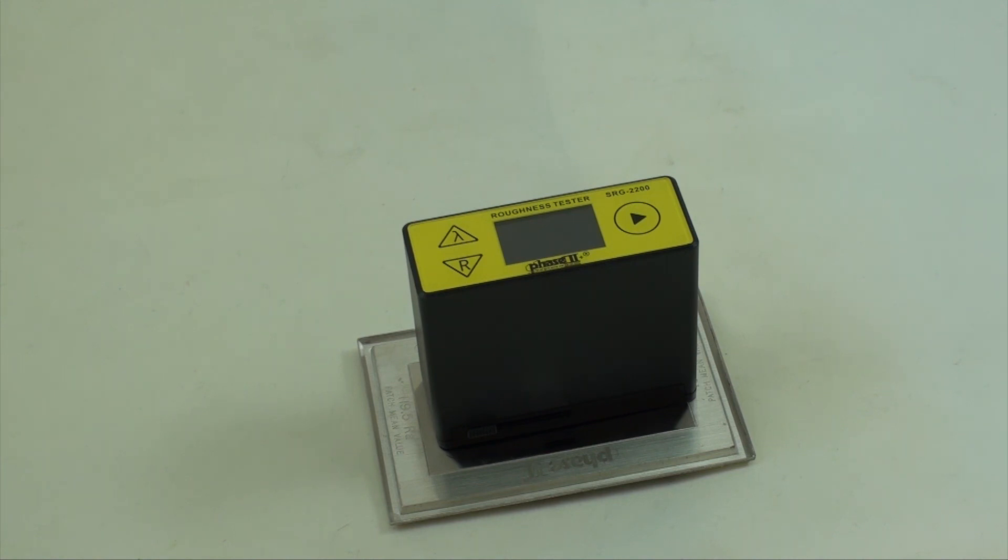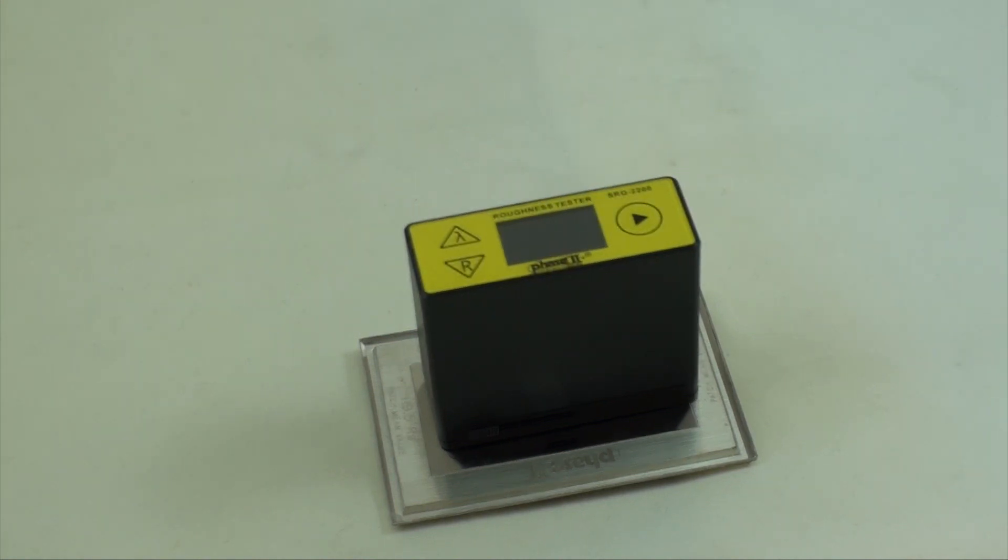These include maximum surface roughness of 10 microns or 400 micro inches. As you can see, the SRG2200 is a handheld battery-powered instrument with graphic display and controls in the front and a built-in stylus that moves forward and returns upon taking surface roughness samples automatically.